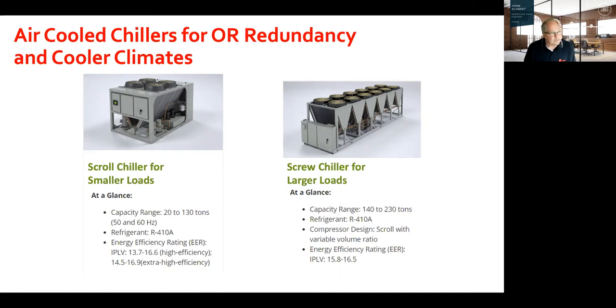And if you don't have an air-cooled chiller that you can just fire up for your ORs or your other critical areas, it can take 6-8 hours to get that tower filled back up and run your critical areas on those warmer days. So it's a good idea to consider that. It's also helpful if the main plant goes down, for those of you in the south, to have that redundancy on your critical areas, especially your ORs. Next slide, please.